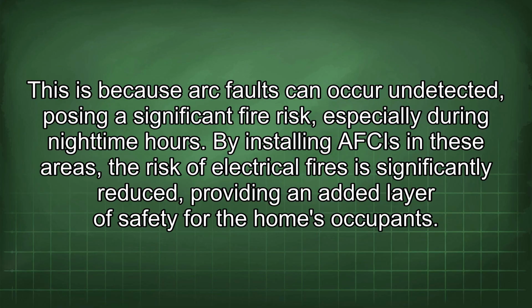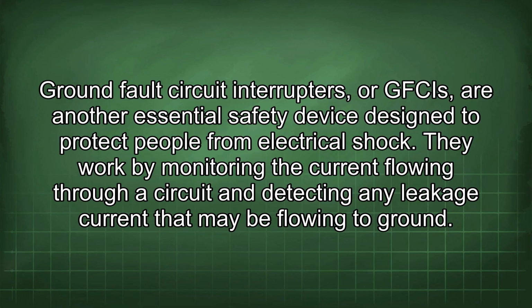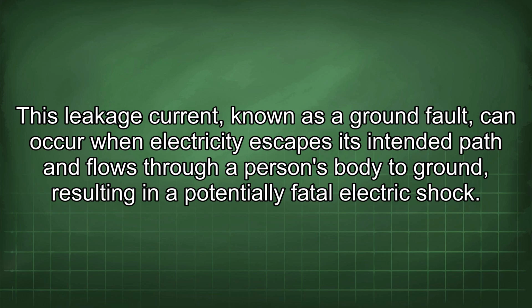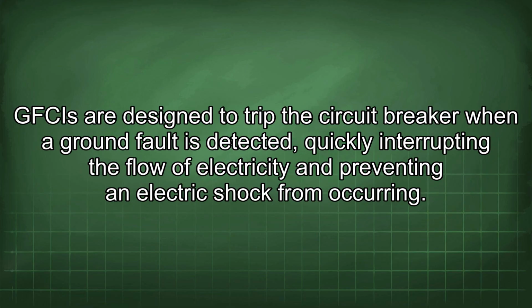Ground fault circuit interrupters, or GFCIs, are another essential safety device designed to protect people from electrical shock. They work by monitoring the current flowing through a circuit and detecting any leakage current that may be flowing to ground. This leakage current, known as a ground fault, can occur when electricity escapes its intended path and flows through a person's body to ground, resulting in a potentially fatal electric shock. GFCIs are designed to trip the circuit breaker when a ground fault is detected, quickly interrupting the flow of electricity and preventing an electric shock from occurring.